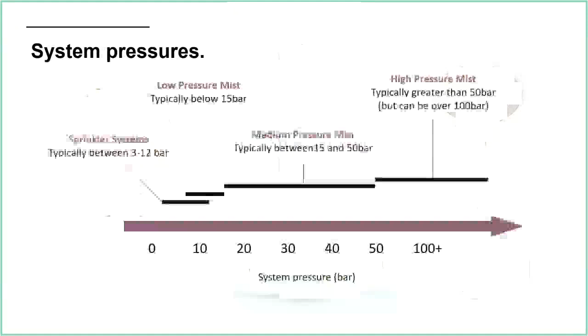System pressures, let's talk a little bit about that. For sprinkler systems, under 12845, we talk about a maximum of 12 bar. Sometimes you do get a little bit higher than 12 bar if you've got a high-rise building. Some of the risers and some of the equipment by the installation control valves may well be higher than 12 bar. But the water behind the sprinkler heads goes to a maximum of 12 bar, and typically a lot lower than that. Again, we don't want to add pressure to the system unnecessarily. So essentially, we're going to have the lowest pressure we can while still guaranteeing the minimum pressure at the sprinkler heads.